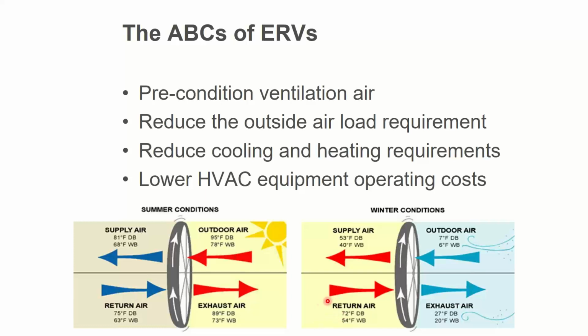Instead of exhausting it straight out of the building, I run it through a heat exchanger, and that heat exchanger sends the BTUs over to the outside air, and that 7 degrees gets warmed up to 53 degrees in this example. And then the 53 goes into the rest of the hydronic heating coil, gas furnace, whatever you got. So I'm going to use the heat from the exhaust air to preheat the outside air.